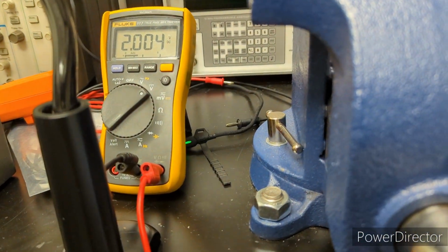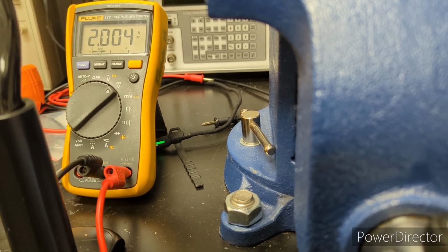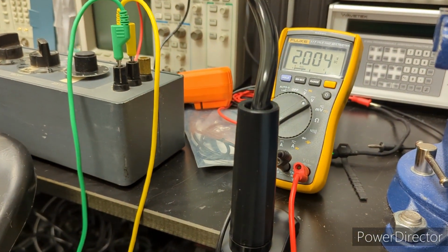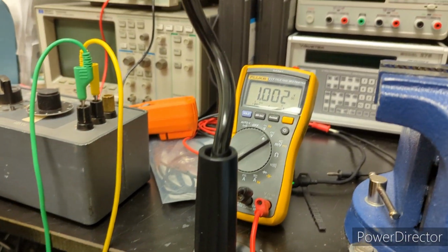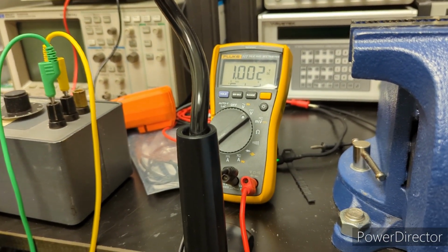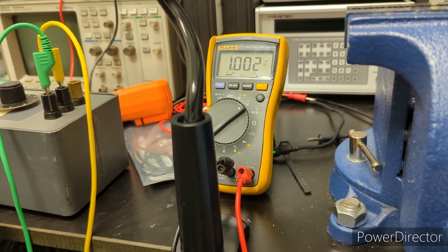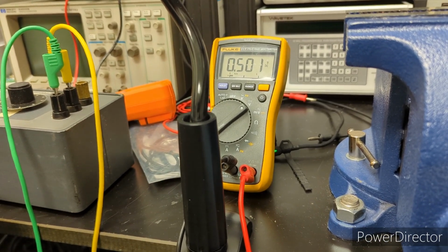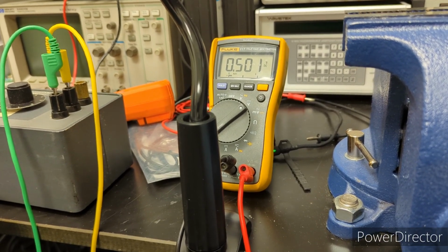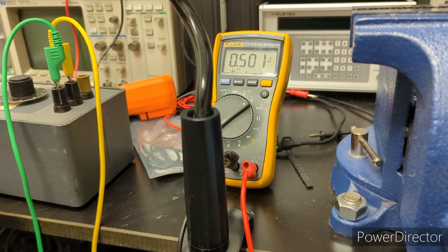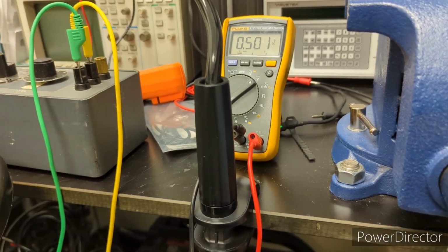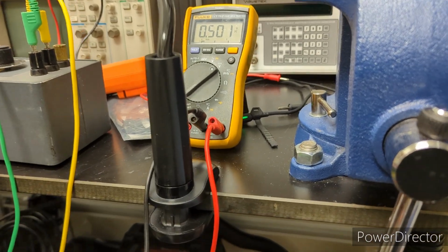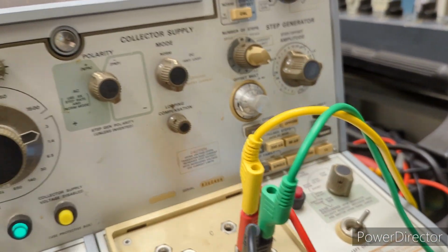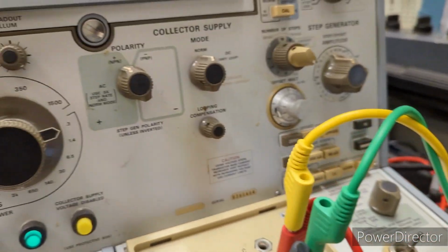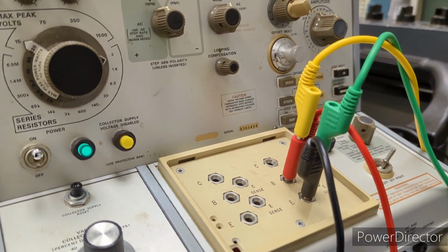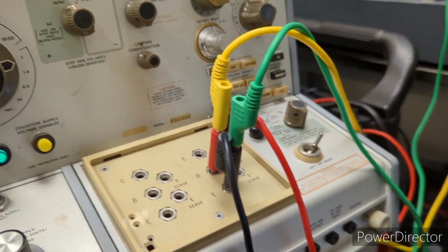We should be getting 2 volts, 2 volts plus or minus 0.04. That looks good. 10 microamps, getting 1 volt plus or minus 0.02. Also looking very good. And then for 5 microamps, we should be getting 0.5 volts at plus or minus 0.01. So also looking very good. So the amplitude switch is looking good as far as accuracy. Again, this was something we couldn't test in the last video, but it's looking great this time around.